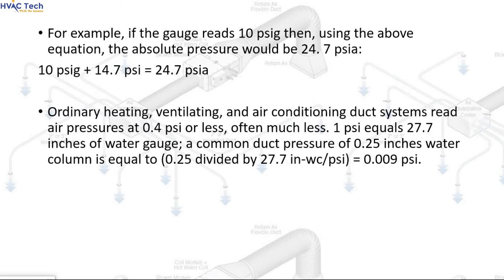10 psig + 14.7 psi = 24.7 psi. Ordinary heating, ventilating, and air conditioning duct systems read air pressures at 0.4 psi or less, often much less. 1 psi equals 27.7 inches of water gauge. A common duct pressure of 0.25 inches water column is equal to 0.25 divided by 27.7 in WC/psi, which equals 0.009 psi.